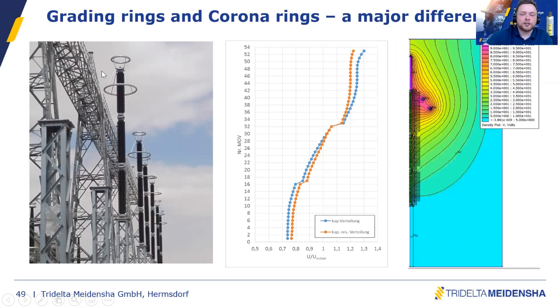So when we apply voltage to an electric device, it will have a kind of electromagnetic behavior, and the higher the voltage, the stronger this influence is. And then the design of the surge arrestor is of interest, because if you have sharp edges, they behave like an antenna, and something happens that we call external partial discharge. It's like electromagnetic waves are coming out of the surge arrestor upper part, and we want to prevent this because this is producing radio interference. And that's why we are applying a corona ring, which is somehow shielding the top of the surge arrestor with a very round shape. So this is the best shape you can have to cover the surge arrestor from the electric field and to prevent RIV or corona to appear.